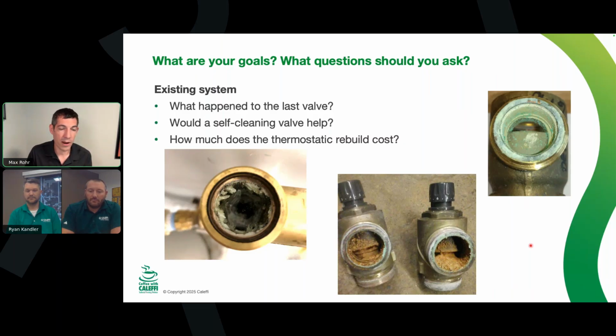However, that's a lot of brass in those, and it's not just a Caleffi thing, but anybody's thermostatic mixing valve. If you're replacing the valve body every 6 months, it might be a cause to move to a digital mixing valve. Maybe less expensive to do that in some cases too.